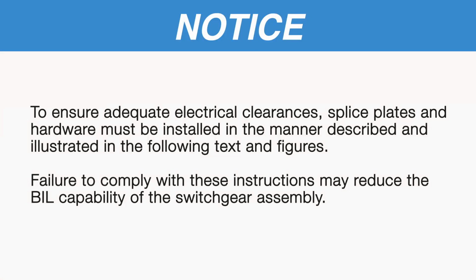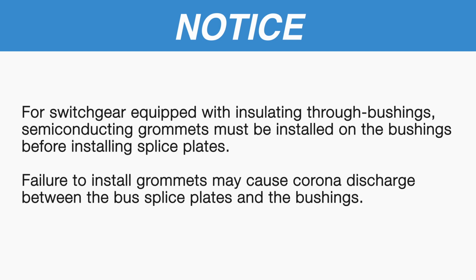Note: to ensure adequate electrical clearances, splice plates and hardware must be installed in the manner described and illustrated in the following text and figures. Failure to comply with these instructions may reduce the BIL capability of the switchgear assembly. For switchgear equipped with insulating through bushings, semiconducting grommets must be installed on the bushings before installing splice plates. Failure to install grommets may cause corona discharge between the bus splice plates and the bushings.